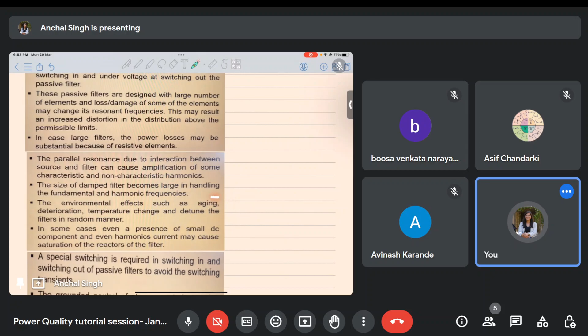Then again, the sizing of these filters is very high. And then there are environmental effects such as aging, deterioration, and temperature change, which affect the filters in a random manner. So right when we are installing these filters, we predict a kind of working, but with time, age, temperature change, weather change, all these conditions, the working of this filter and its parameters will change. Then in some cases there is a small DC current present in the distribution system, and the presence of this DC component or even harmonics may result in the saturation of reactors. Again, when the reactor saturates, heavy currents will be drawn, right?